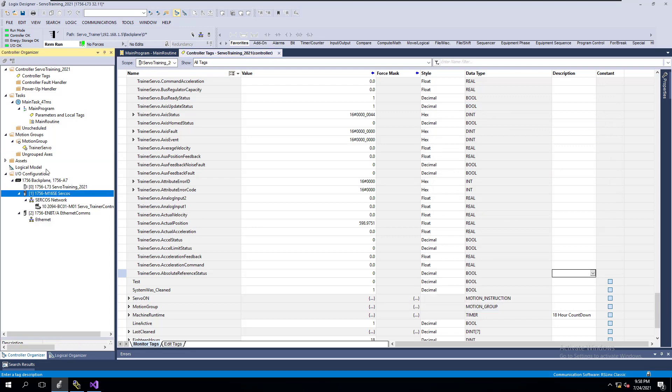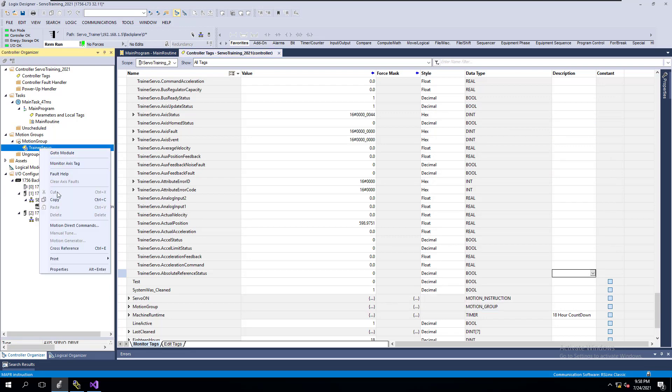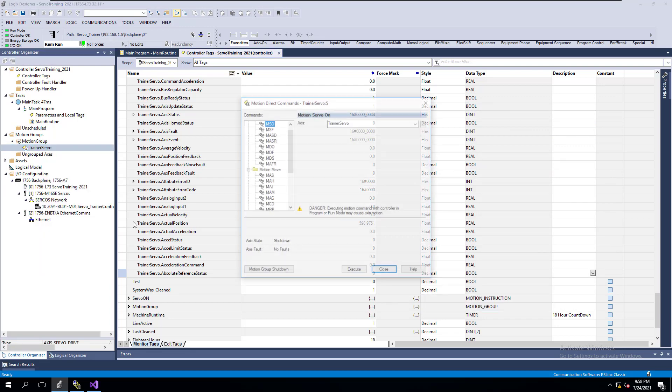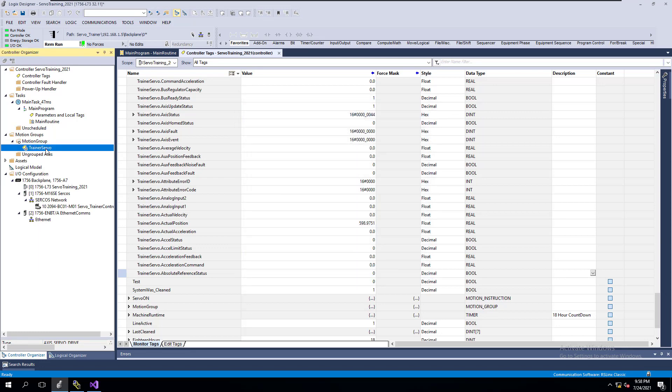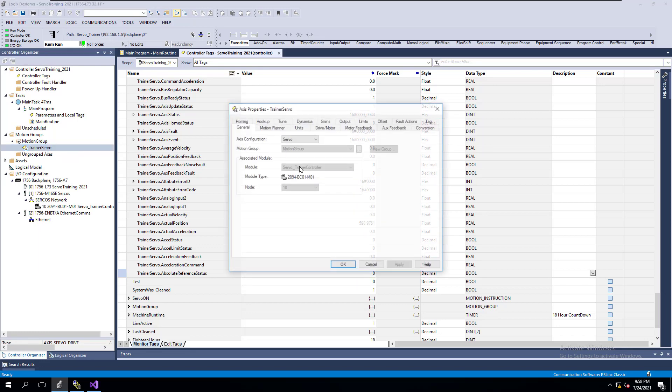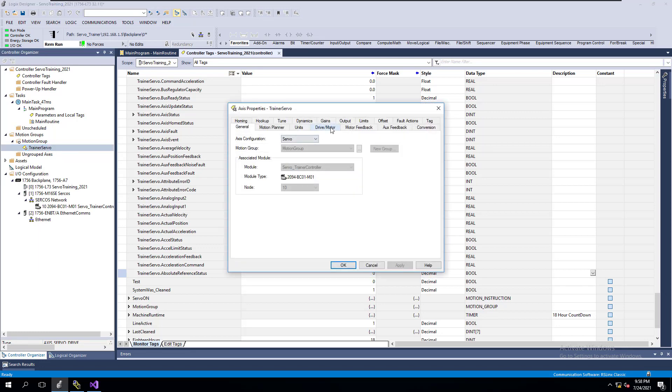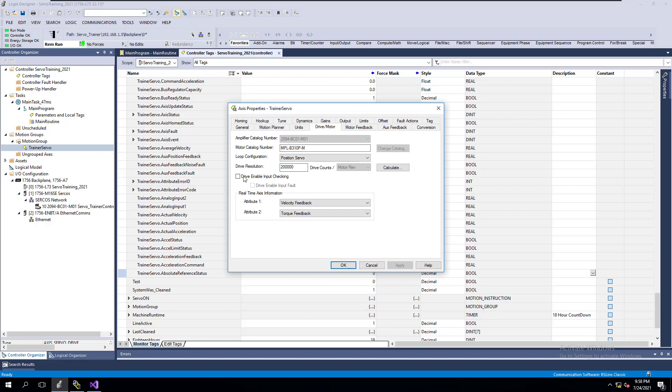Now just to show you, that was to show you if you do have the problem, where you have the error, where to go to look. You need to verify your system right here. Most of the time that happens, it's going to be the drive input is checking for that drive enable. So you need to make sure your drive enable is actually set.